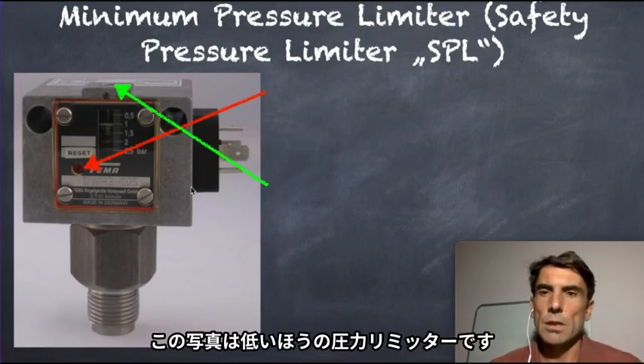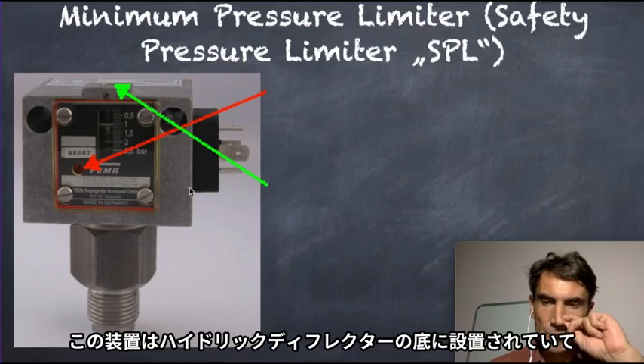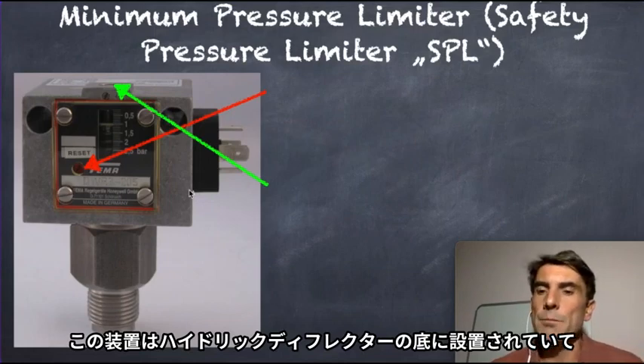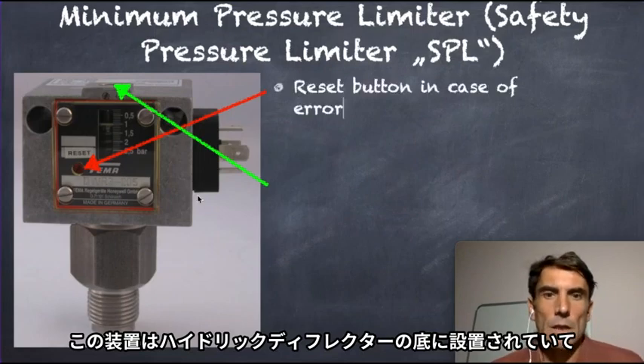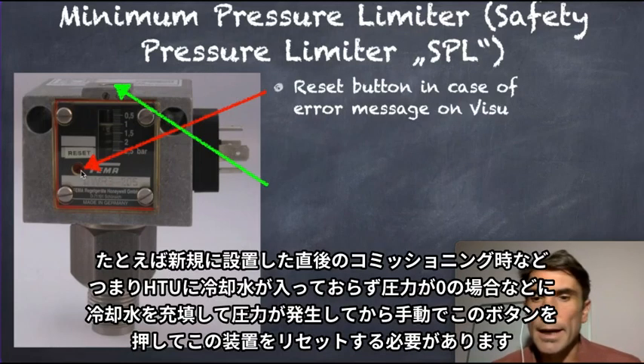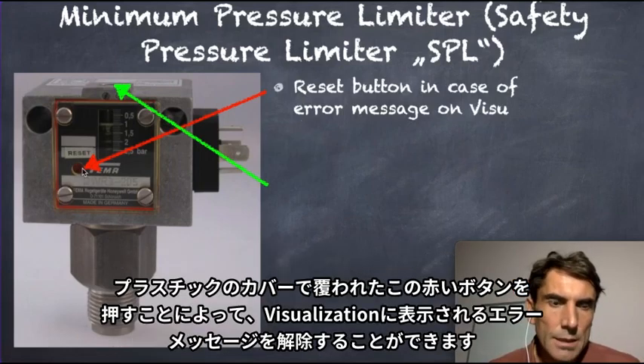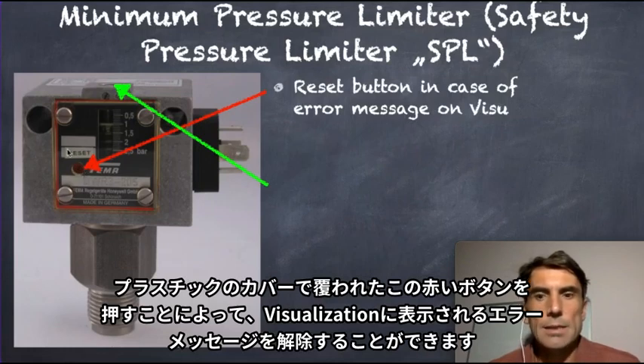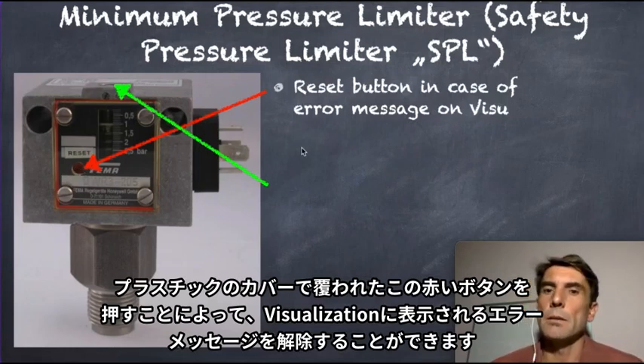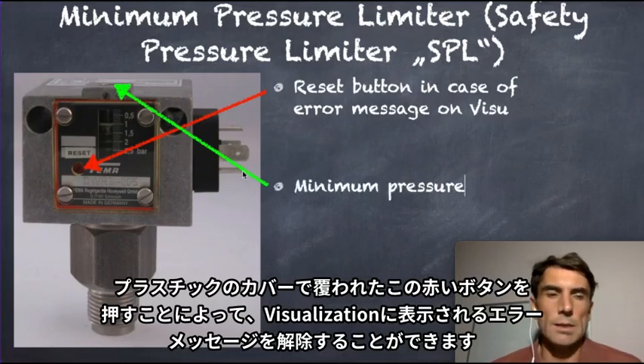We have here the minimum pressure limiter. This is the low pressure measurement tool or switch, which is mounted on the bottom of the hydraulic separator. We have here the small red button. Especially with a new commissioning, there will be no water, so no pressure inside of the HTU. That means after filling the water and raising the pressure, we have to reset the switch manually. So you have to do it by hand. There is a small red area behind this plexiglass where you have to press the button to reset the error message on the visualization.